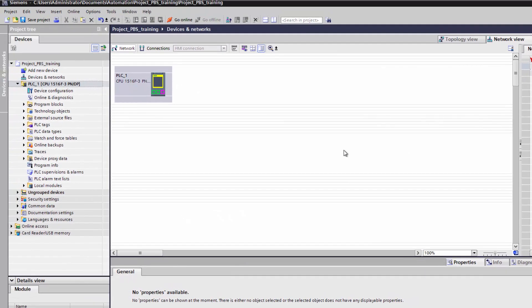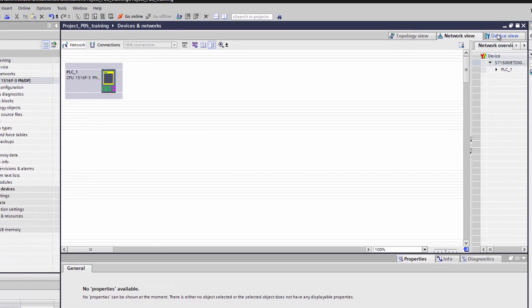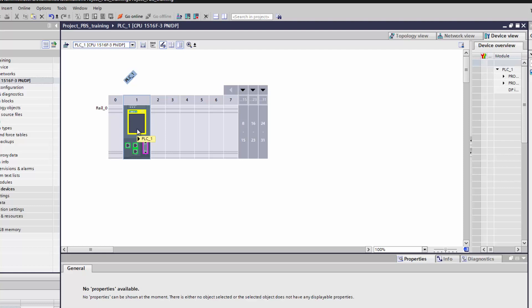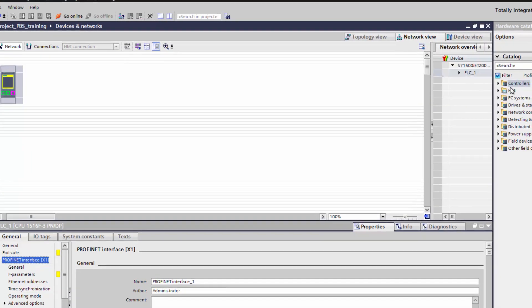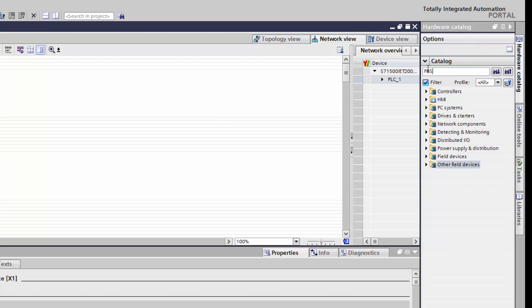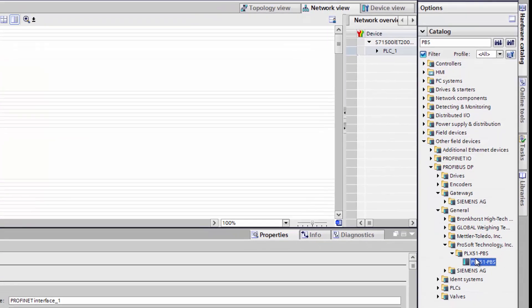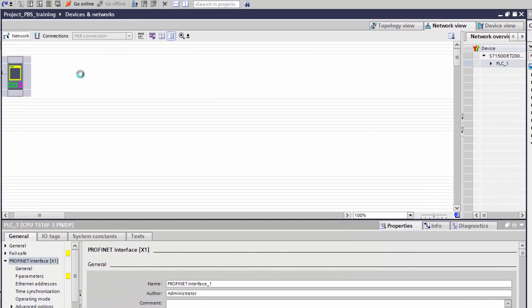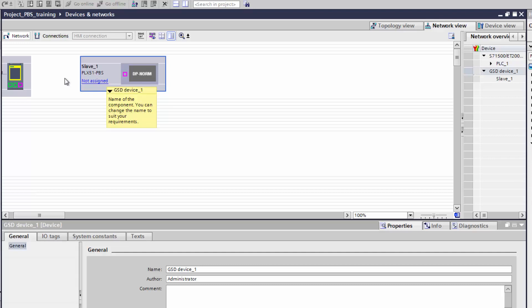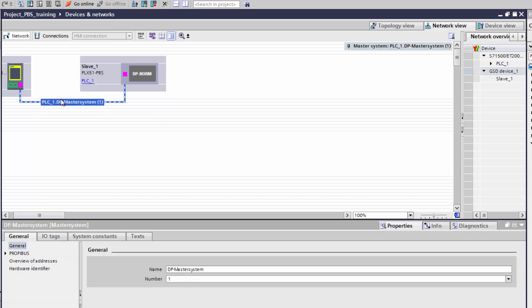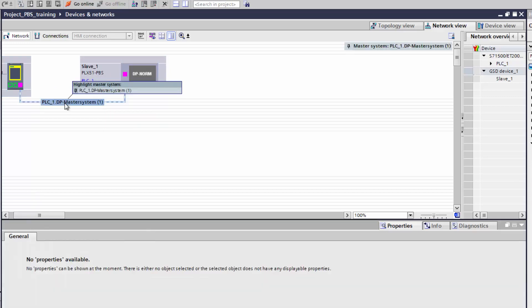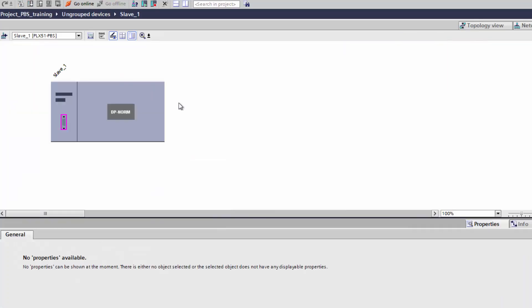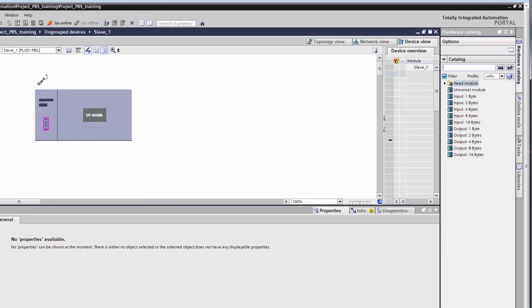So now we'll add our slave device. In the Device View, you can see we have a rack with a controller in slot 1. I'll go to the Network View tab, and then click on the Hardware Catalog tab over on the right side of the interface. Here we can drill down, locate our PLX51 gateway. You can just type PBS into the filter to locate it quickly. Now once you get to the PBS itself, drag and drop it into the Network View with the controller. We want to connect this slave to the controller's DP Interface 1. So just click on the purple PROFIBUS port icon on the module, and drag it to the corresponding port on the S7. Right-click on the gateway and select Device Configuration.